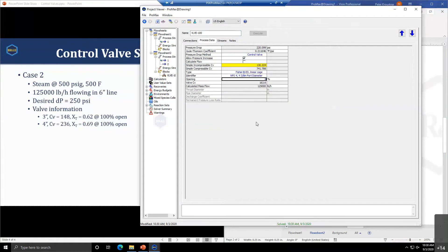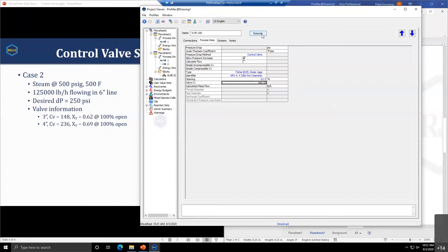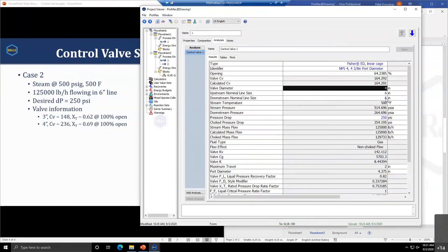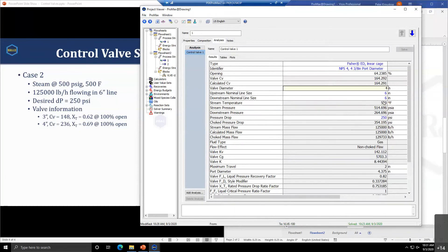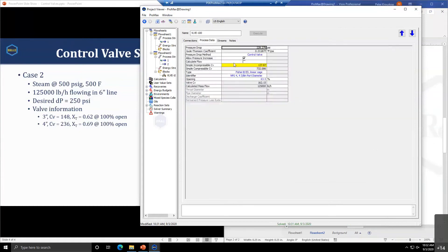If we went to 63.5% open, we get closer to our 250 pound pressure drop. The reason this pressure drop is slightly different from what's calculated in the analysis is because of the size difference between the pipe and valve. The calculations here account for the reducers involved in taking the pipe from six inches down to four inches and back up to six inches. That aspect of the pressure drop is not present in the valve object system because everything is assumed at four inches.